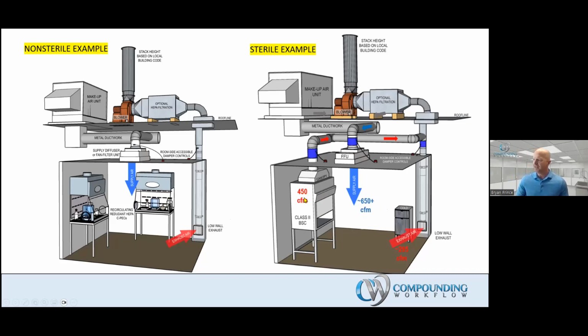At 450 CFM going out of the building, if this air handler wasn't built specifically to add another one, I can't add another hood, because there's not enough capacity for another 450 CFM out of the building. So Bob made a stellar point—you've got to think about scale. Maybe you'll always have just one biological safety cabinet, but if you ever think there could be 2 or 3 at scale, you need to absolutely consider that during the design and construction phase.